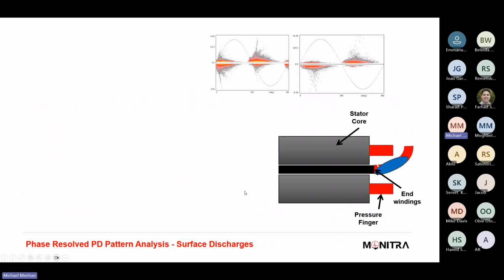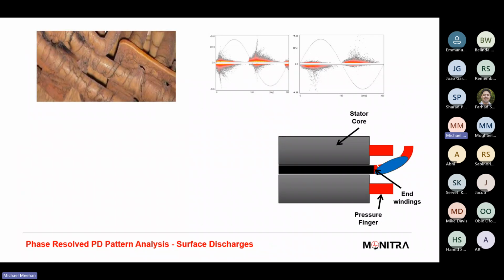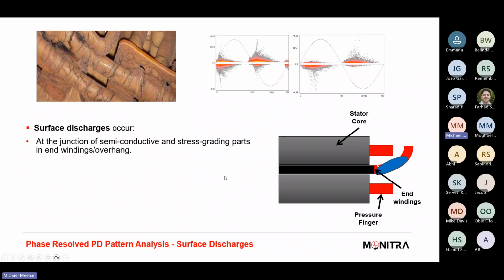So if we think of the stator core, we've got the end windings. The end windings tend to be quite a weak spot, I guess, in the way the motor is constructed. Just by nature, the supports around the end windings are just not as good as when they're in the slots and in the wedges and tightly compact. So the end windings do have to go through a lot of stresses. Obviously, we mentioned earlier about the arduous stop and starts of the machine. Those stops and starts create intense magnetic stresses, and those end windings can jolt, they can move. That movement can cause vibrations.